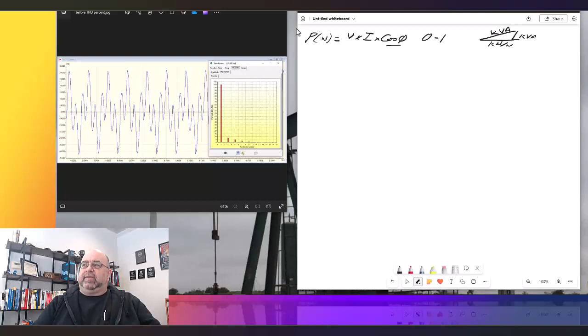So phase angle, when I talk about power factor, I have kVA or VA, kilowatts or watts, and kVAR. There's an angle present — that angle is phi, and the cosine of that angle gives the number you usually see. So when they say they need a power factor of say 0.9, that's the result of the cosine of that angle, somewhere between 0 and 90 degrees. Now 90 degrees, of course, you never want to achieve — that would be completely out of phase. But in any case, we have that first, so we're going to use this.